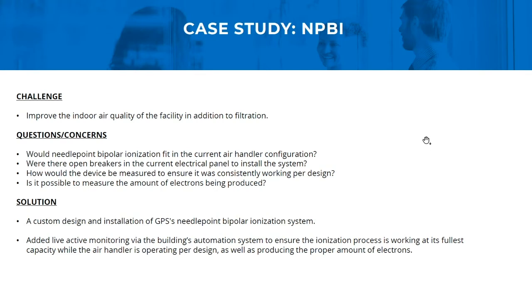We've got one more case study here on needlepoint bipolar ionization. It's a little different than the previous case study. The facility was able to increase their filters to a MERV 13. However, the owner was looking for something more, in addition to the ASHRAE recommended MERV 13 upgrade. So the challenge here was, how can we improve our indoor air quality above and beyond a MERV 13? We looked at a multitude of options and ultimately came down to needlepoint bipolar ionization as being the best option for them. So our solution here was, we designed and installed a custom Global Plasma Solutions needlepoint system for them.